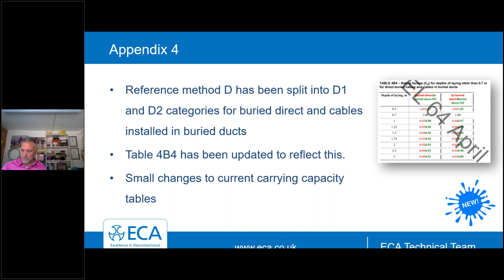Appendix 4: reference method D has been split into D1 and D2, for cables buried in ducts and cables buried direct. Some small changes have been made to reflect this in the current carrying capacity tables - just a small update there in Appendix 4.